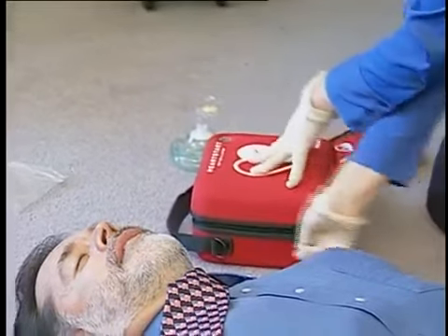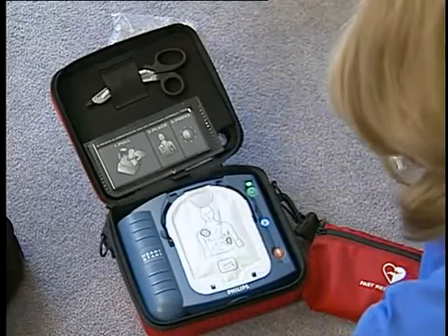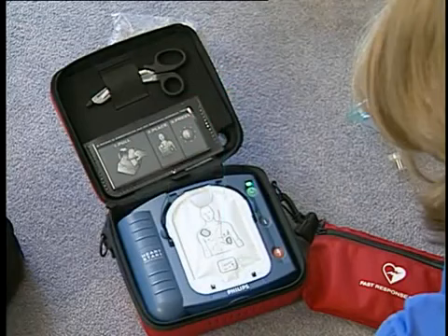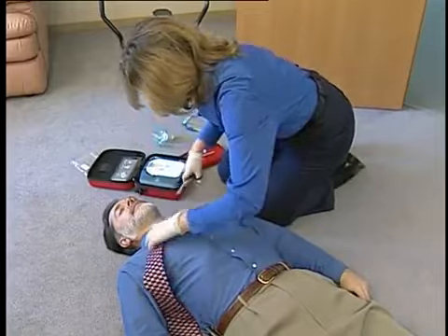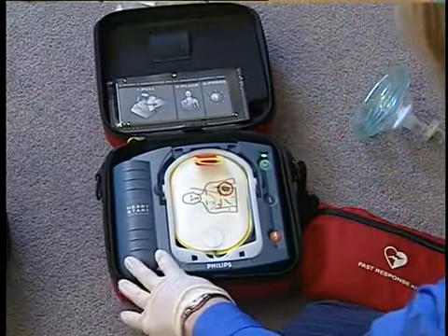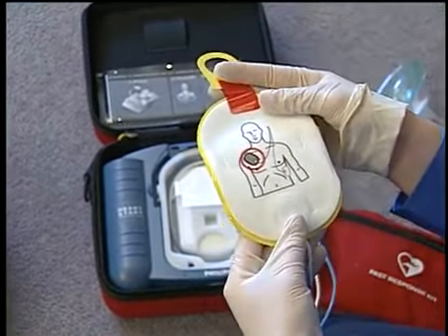Using the HeartStart on-site defibrillator is very easy. Place the defibrillator on the same side of the patient that you are on, near the patient's head. If stored in its optional case, unzip the case. Pull the green handle to remove the hard cover of the pads cartridge — this will automatically turn on the defibrillator. You can also turn it on by pressing the green on/off button. The HeartStart on-site will start giving you clear, calm instructions timed to match your pace. Remove the clothing from the patient's chest, cutting it off if necessary. Then peel the film seal from the cartridge and take out the pads.